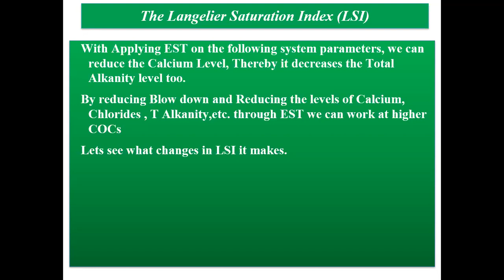So we applied the EST, and EST will obviously reduce your blowdown since you are reducing the levels of calcium, chlorides, and alkalinity, and therefore we can work at higher COCs. Let's see what changes in LSI it makes. You can see that the temperature is 32, the same. pH also remains the same. The TDS is increased a bit, but the calcium is actually reduced. TDS increased means the harmful elements from the TDS are being taken out. You can see in the previous slides that calcium was a bit higher, but alkalinity was also a bit higher. Based on that, we are getting an LSI of 0.87.